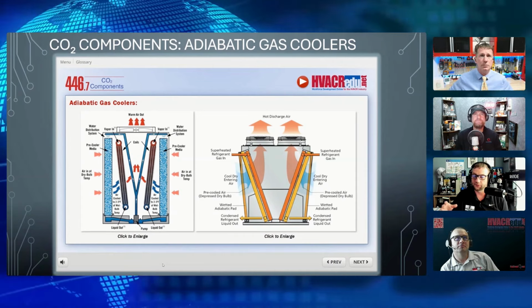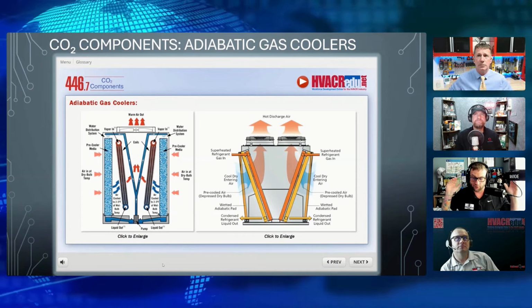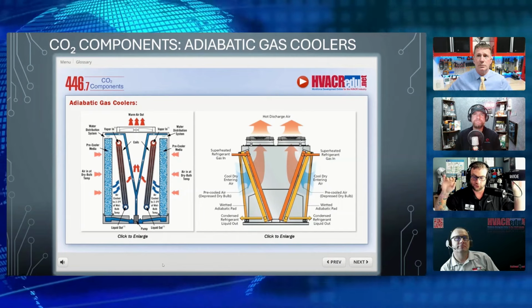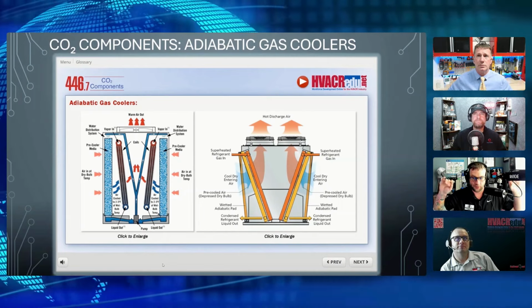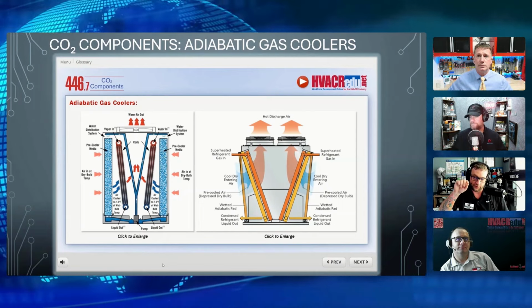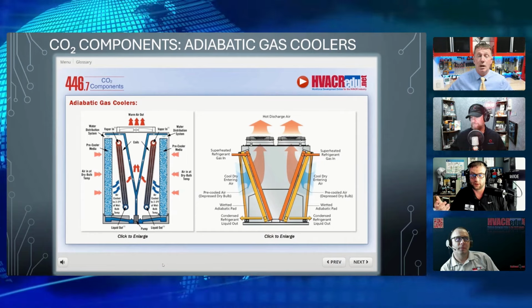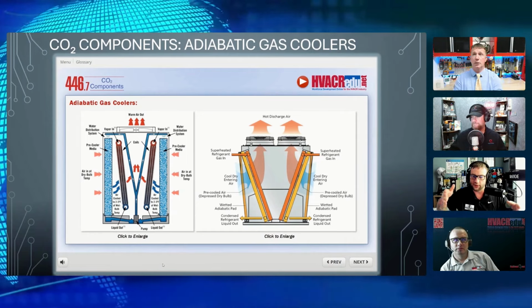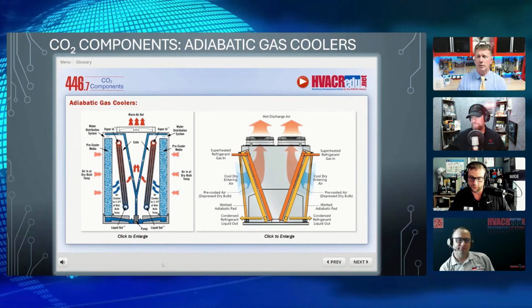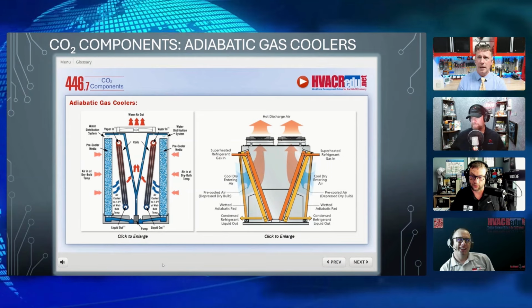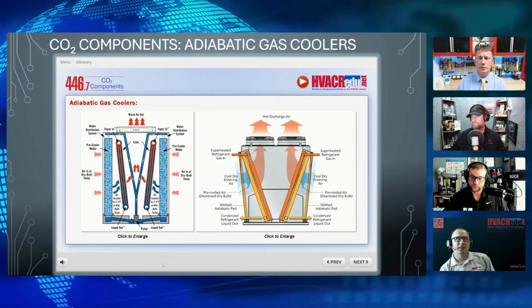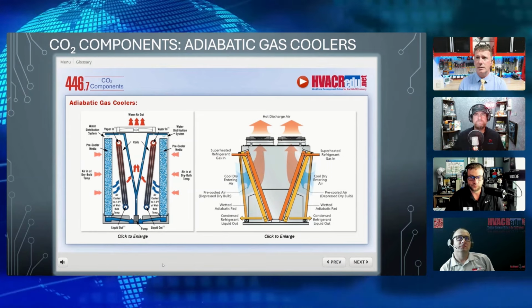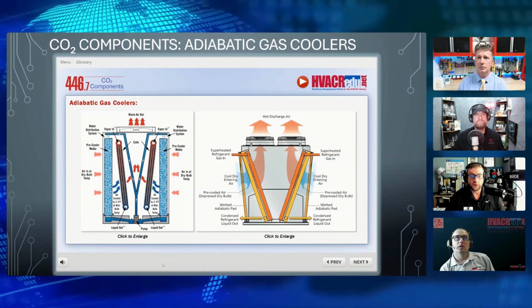Very cool. So some systems don't have a pump, where it's just whatever water they are calling for, based on what it's trying to do with the enthalpy outside. If it just has to release a little bit of water, that's what it's going to do. If it has to release a lot of water, it will, because we're trying to utilize as much of the water as possible, because water is a commodity like anything else. Absolutely. Yeah, so some of these are non-recirculating systems. They're just direct water flow.